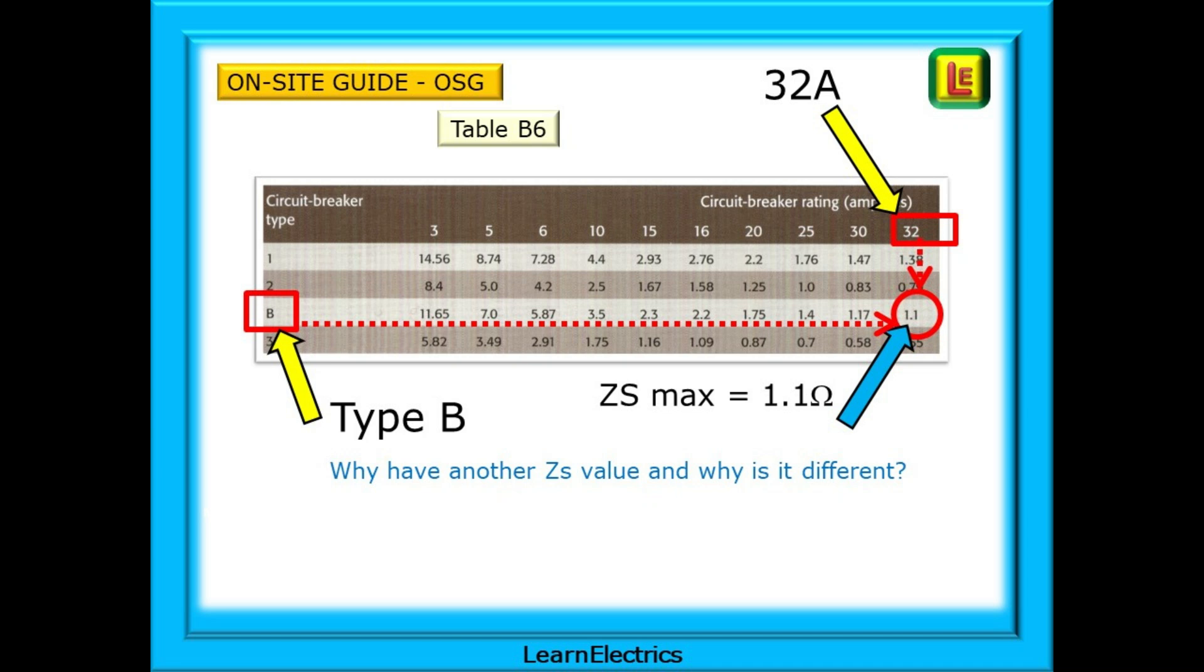ZS maximum is just 1.1 ohms, different again to the 1.44 that we started with and the 1.37 tabulated value. Why do we have another ZS value and why is it so very different?